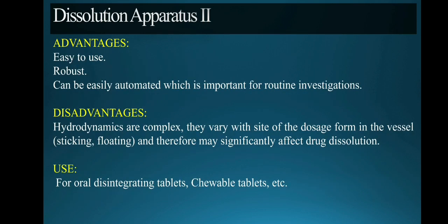So its advantages include easy to use, robust, can easily be automated. And disadvantages include that hydrodynamics are very complex, so there may be possibilities that it may affect the dissolution. The use of this apparatus is for dissolution, oral disintegrating tablets, and for chewable tablets.